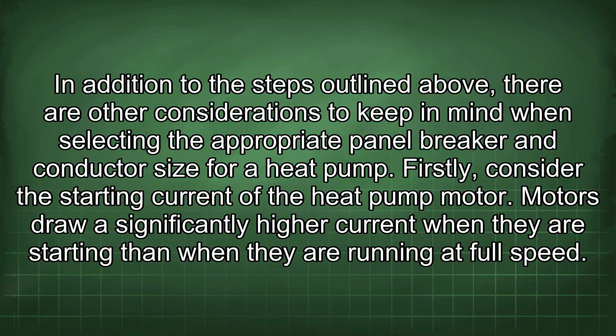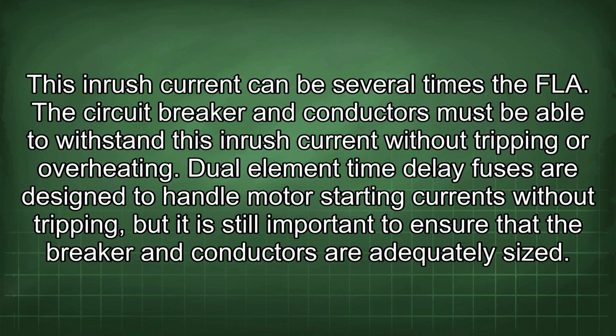In addition to the steps outlined above, there are other considerations to keep in mind when selecting the appropriate panel breaker and conductor size for a heat pump. Firstly, consider the starting current of the heat pump motor. Motors draw a significantly higher current when they are starting than when they are running at full speed. This inrush current can be several times the FLA. The circuit breaker and conductors must be able to withstand this inrush current without tripping or overheating.